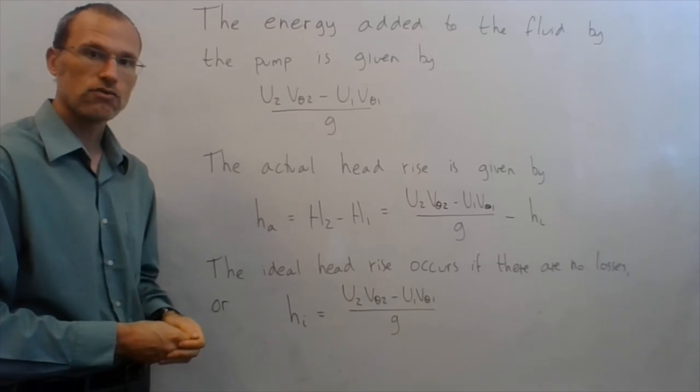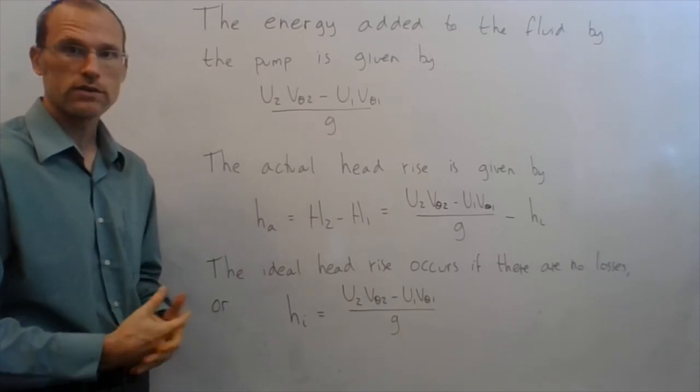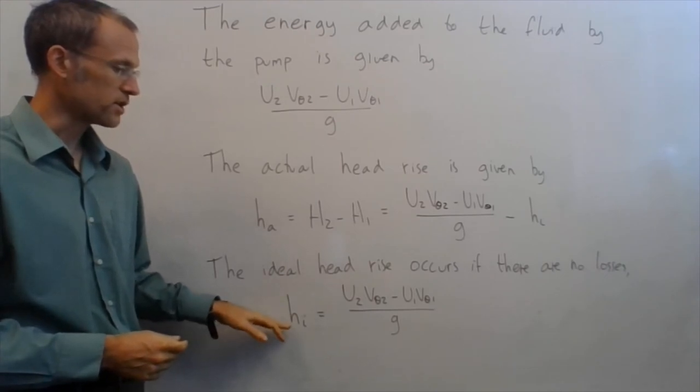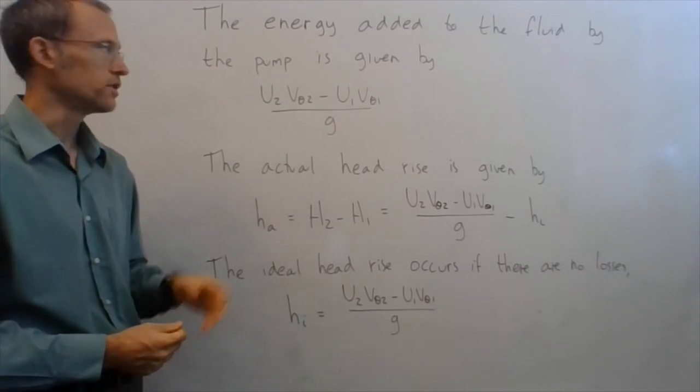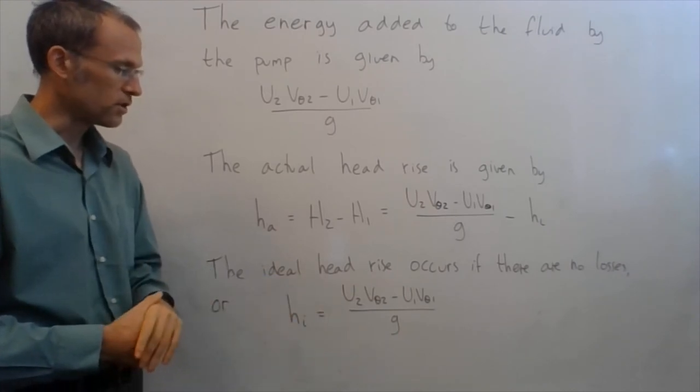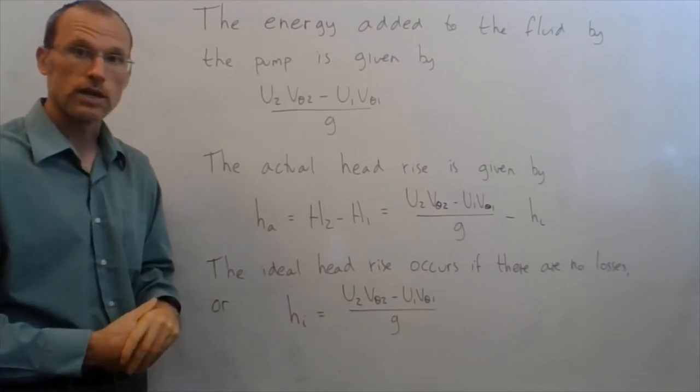In the ideal case, I have an ideal head rise, where there are zero losses, so zero losses just means hl is zero, so my ideal head rise is just equal to the energy being put in, so h_i is u2 V theta 2 minus u1 V theta 1 divided by g.